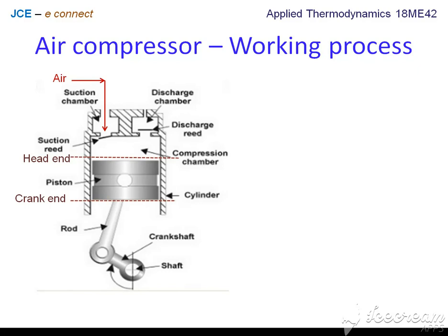Looking at the working process, the working of an air compressor can be divided into four processes. Number one is the suction process, during which the inlet valve opens at the suction chamber and air from the atmosphere is let into the cylinder. This happens because of the pressure difference between the ambient pressure and the pressure prevailing inside the cylinder. During this process, the piston moves from the head end to the crank end at a constant pressure condition.